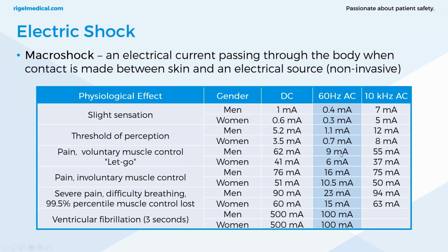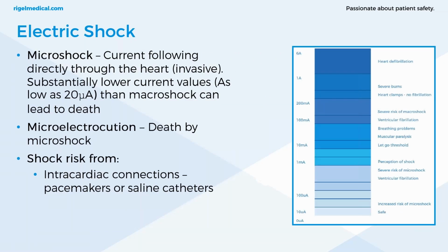So the results from macro shock, we've got loss of involuntary muscle control, currents as low as 10 milliamps or 6 milliamps, and then ventricular fibrillation at currents at approximately 100 milliamps. And when we go on to the next slide and show you the effects of micro shock, we can see that the levels are much lower, in the magnitude of 10 microamps, 20 microamps, you get an increased risk of micro shock.